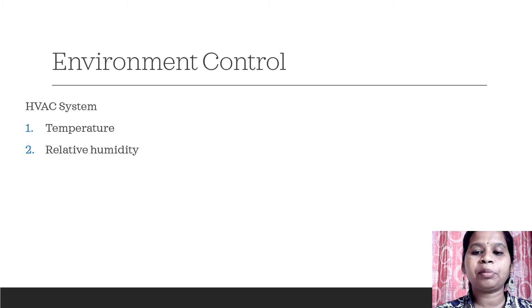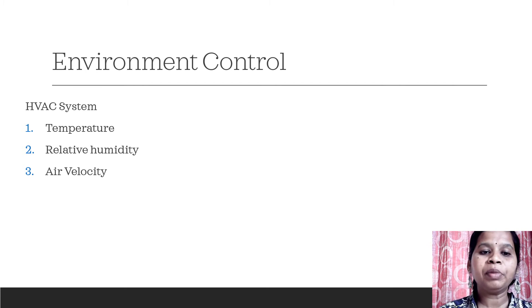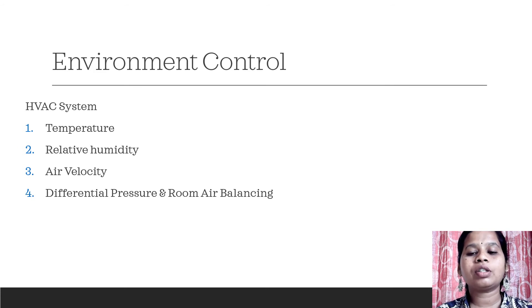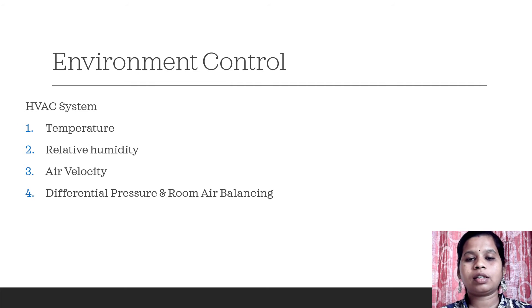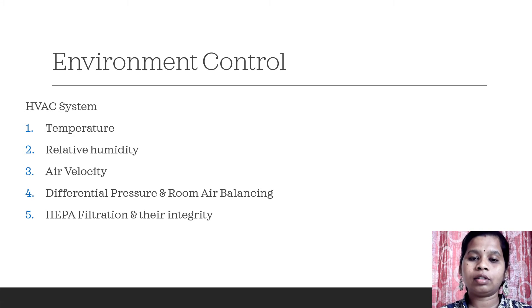Depending upon the product requirement, humidity can be adjusted. Next is air velocity — in case of HEPA filters, the air velocity normally required is between 80 to 120 feet per minute. Next is differential pressure and room-to-room air balance. To maintain the differential pressure in different areas, we are supposed to keep a difference of 15 pascals. This can change with door opening and closing, so the pressure must be adjusted accordingly.